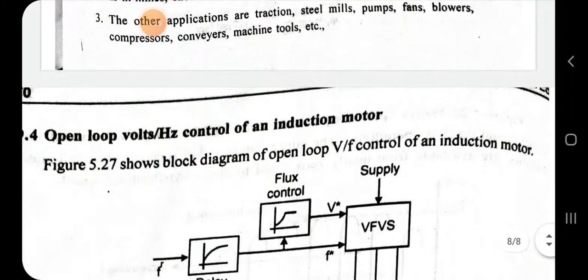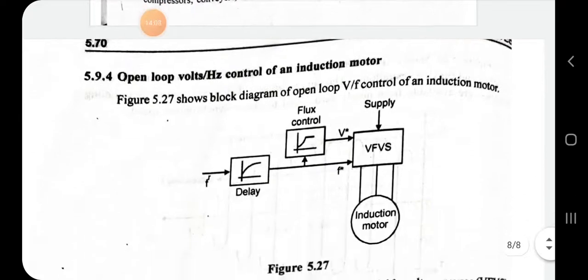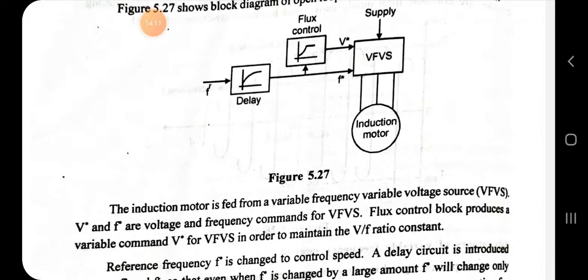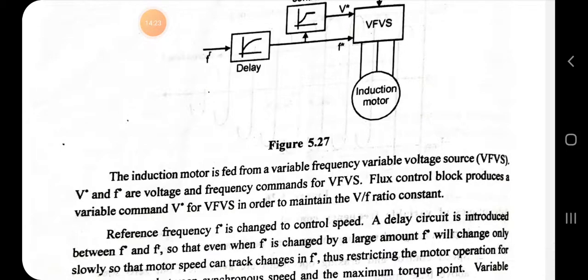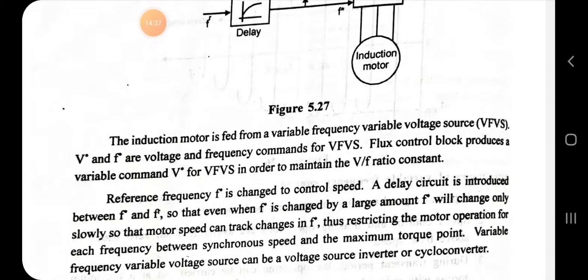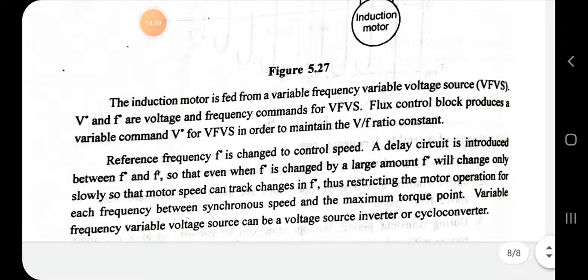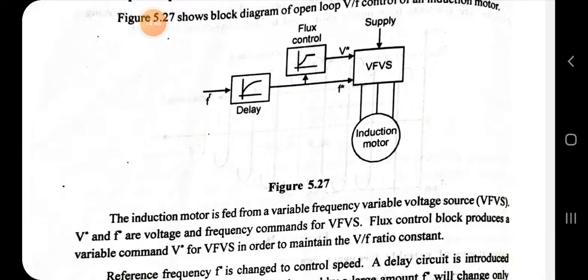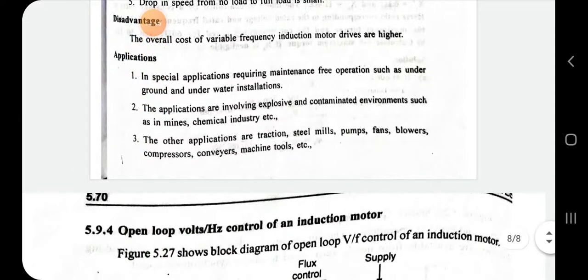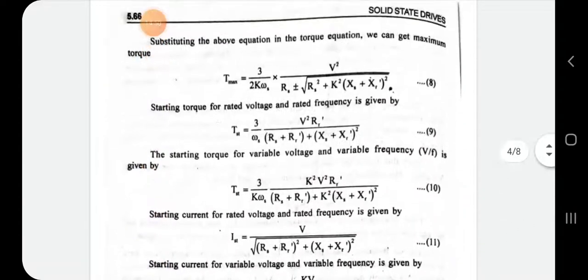For open-loop V/f control of an induction motor, a variable frequency variable voltage source is used. The variable voltage command V* and frequency reference F* are set; by changing V* and F*, the induction motor speed can be varied. A delay circuit is introduced, and instead of a VF drive, a cycloconverter can also be used.